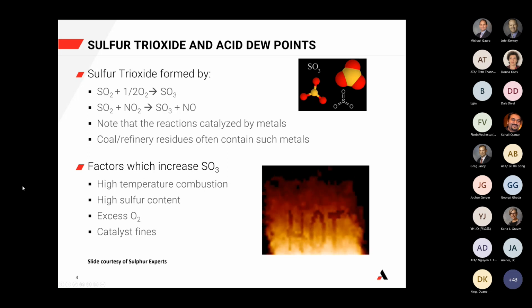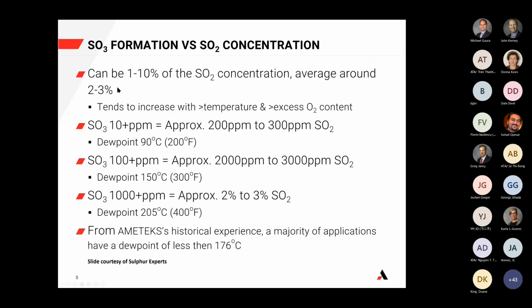So again, the factors that increase the amount of sulfur trioxide are high temperature combustion, high sulfur content, excess oxygen, and the availability of catalyst fines. As we mentioned, anywhere from 1 to 10% of the SO2, and we average around 2 to 3%, can be in the sulfur trioxide form. Just to give you an example, and this data comes from sulfur experts who were very kind to share their slides with us: at roughly 200 to 300 ppm SO2, you're going to see approximately 10 ppm SO3. That's a dew point of about 90 degrees C.